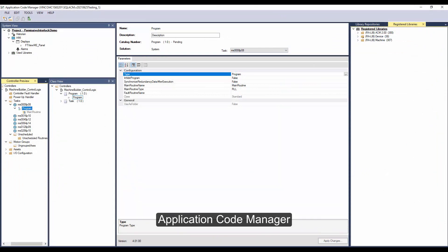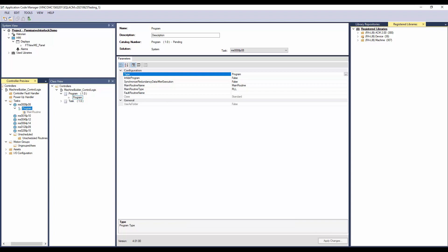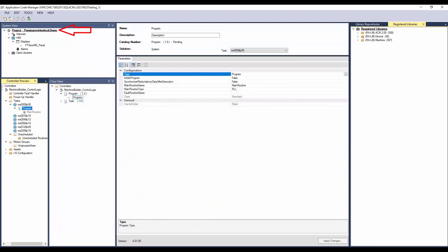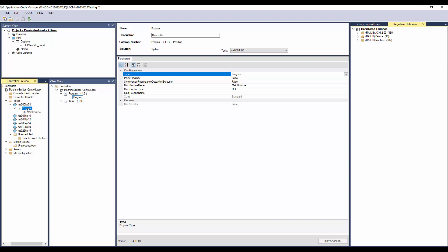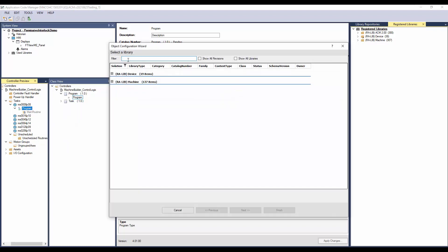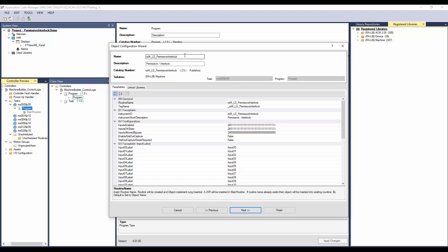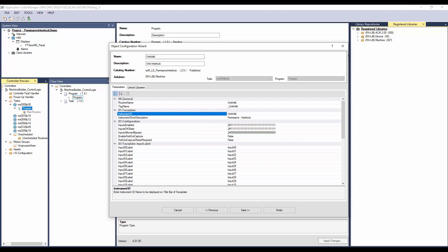In this section I will demonstrate how to instantiate the permissive interlock object in application code manager. The application code manager already has the machine library registered. You need to download the libraries from the Rockwell Automation product compatibility and download center page. I have already created a project, added a controller and display, and also added a program where I will instantiate the permissive interlock library object. To add, right-click on the program and select Add New. In the filter, enter permissive. Select the permissive interlock library object and click Next. I will name the object instance as unit interlock. The routine name and tag name can be modified as required. Modify the instrument ID and description to be displayed on the faceplate.